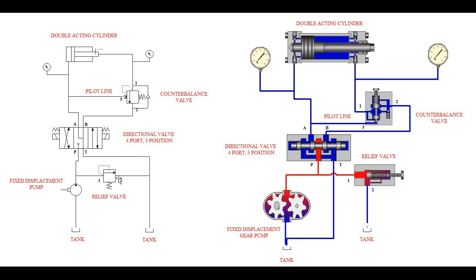The second component is a relief valve, a common component used in hydraulic circuits to control and limit pressures. The way it works is when the pressure from the pump comes, and if there's no path of resistance lower than the setting of this relief valve, you'll get this upstream pressure at port 1 that will actually shift this arrow over to allow flow to go from 1 to 2 into tank.